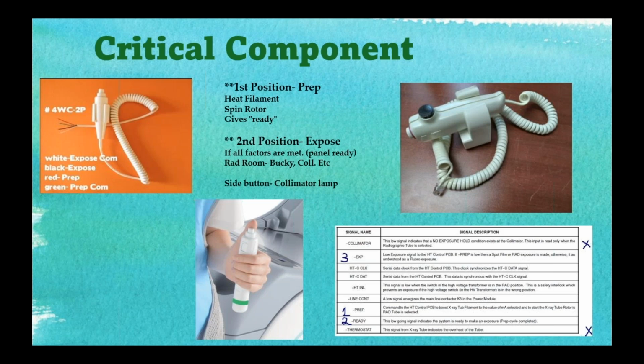After that, let's just say the battery is good in the panel and it's ready to make an exposure. There'll be green lights on the panel. That information is fed back to the control, and if all the factors are met, we push down the second position, and that's when that high voltage is applied to both sides of the X-ray tube, and that's when we have our X-ray. Only while you're holding the switch. If I let go, it's done. It doesn't continue on after I let go of the hand switch.